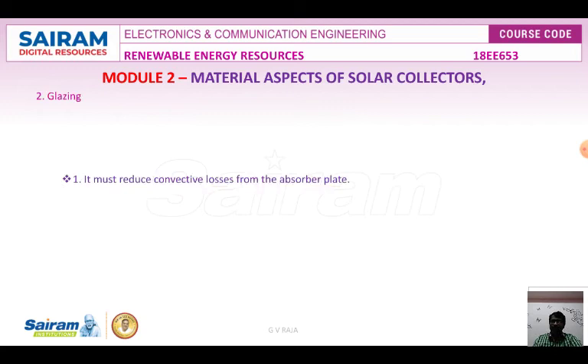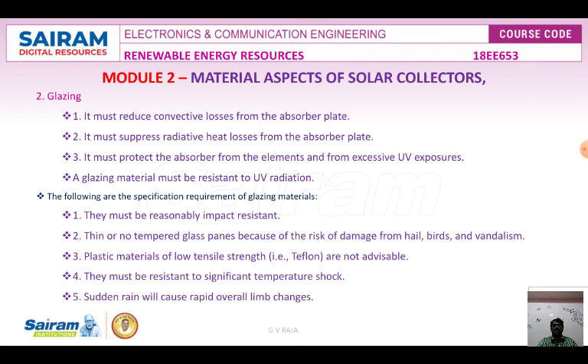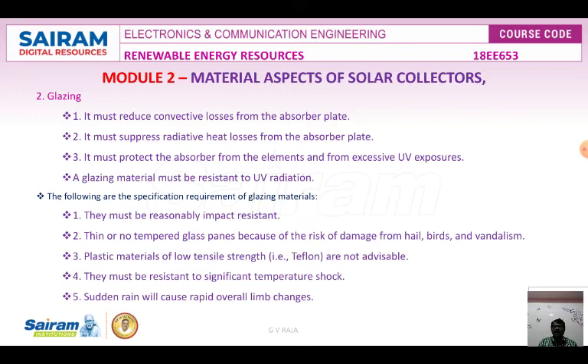The coating must not be so thick that heat conduction through the paint to the absorber material is impacted. The glazing or glassing material is one or more sheets of glass or radiation-transmitting material used as a transparent cover. Its important functions are: it must reduce convective losses from the absorber plate, suppress radiative heat loss, and protect the absorber from elements and excessive UV ultraviolet exposure. A glazing material must be resistant to ultraviolet radiation.